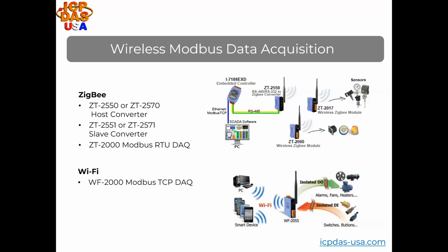Our ZigBee slave converters, ZT2551 and ZT2571, are connected to Modbus RTU devices over RS-232 or RS-485 bus. And the ZT2571 has an Ethernet port for connecting to the Ethernet network. ZigBee supports communication distances up to 2,296 feet or 700 meters line of sight. Each ZigBee end device acts as a repeater, and we also offer repeaters for extending communication distance.